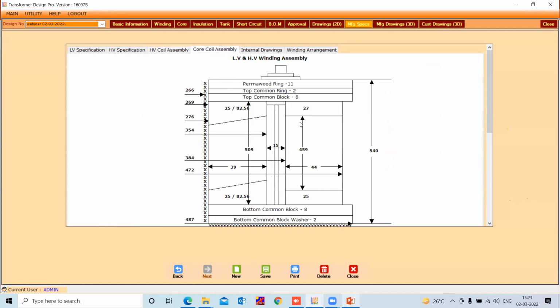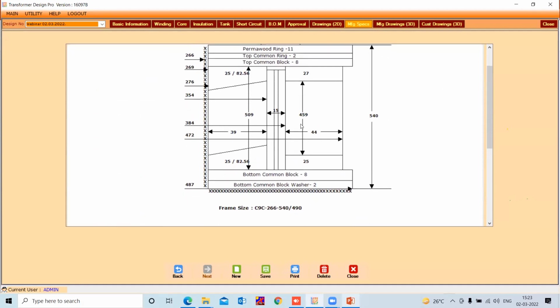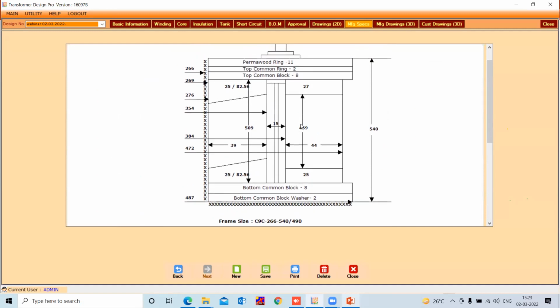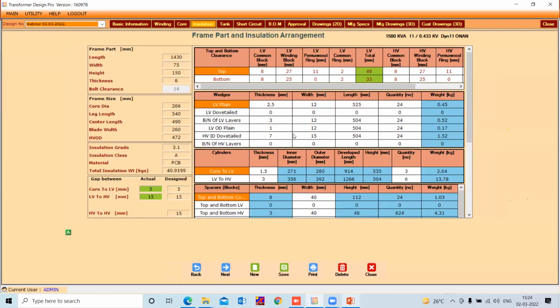And the core coil assembly detail. Here you can see the figures for insulation, like core to LV gap, LV to HV gap, then the electrical and physical height, top and bottom clearances, how we arranged the clearances with the insulation. That information is available over here. And this diagram also you can modify using this insulation page. You can make the insulation arrangement as per your requirement, keeping the same core gap and the LV to HV gap.